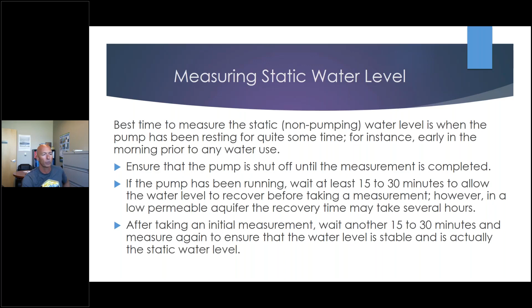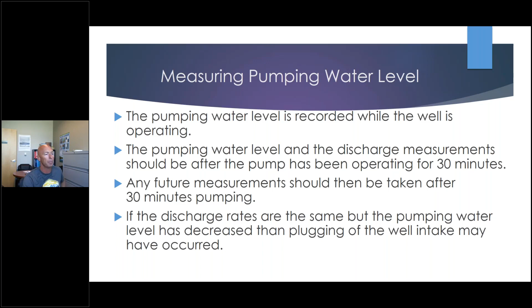The pumping water level is recorded while the well is operating. So again, we need to know where the pump is so that we're not pulling that and causing, you probably have heard of cavitation, that we're not causing cavitation down in that pump, and that we're back to those pumping levels when we first installed the gear. Any further measurements should be taken after 30 minutes of pumping. If the discharge rates are the same but the pumping water level has decreased, then plugging of the well intake may have occurred.